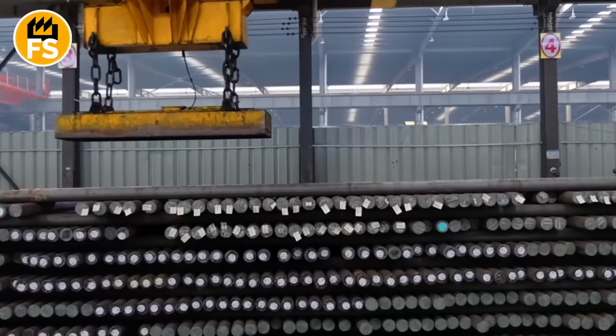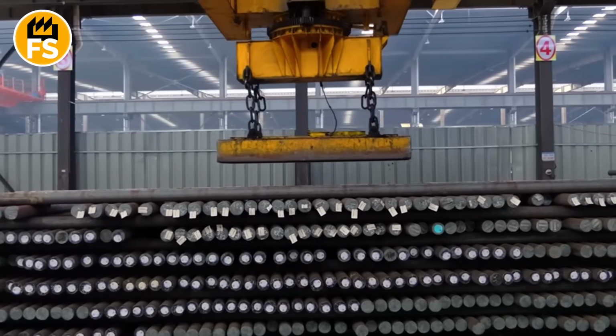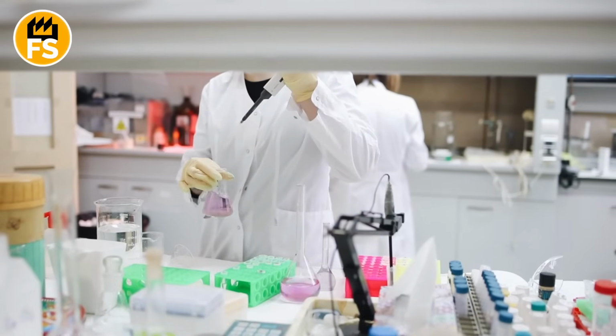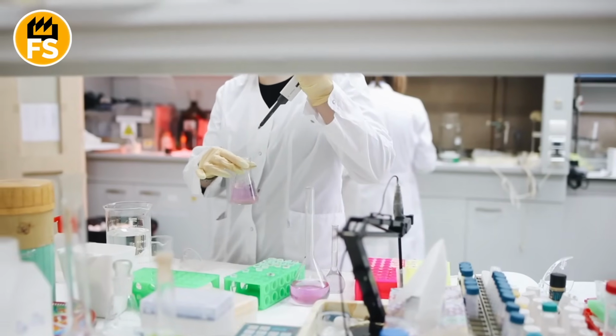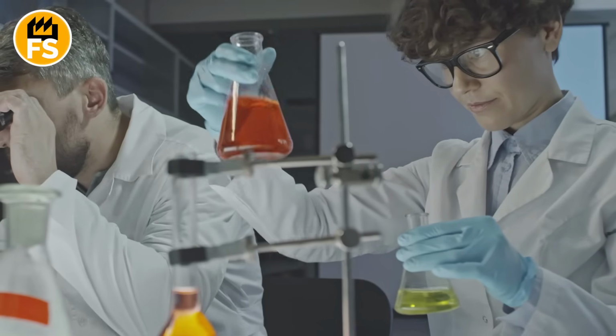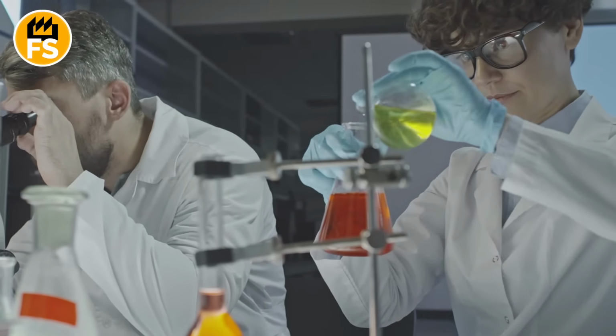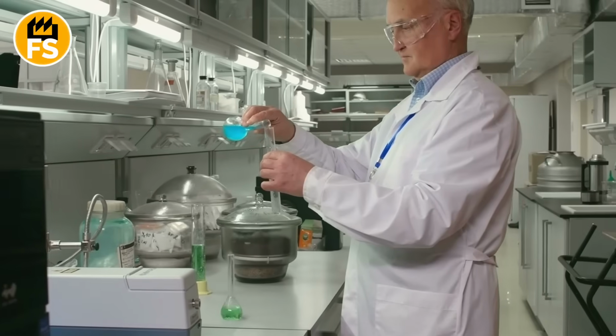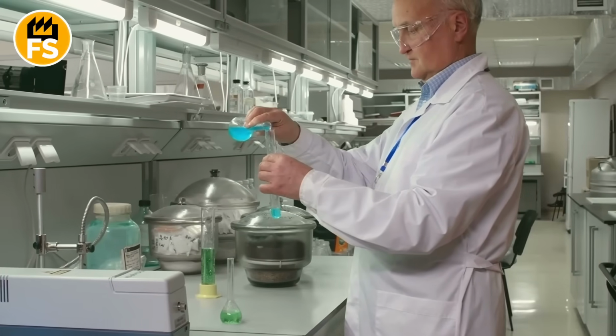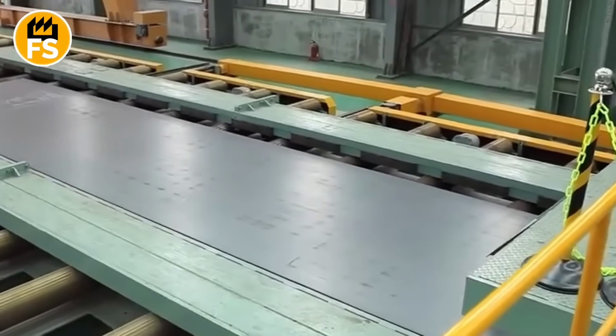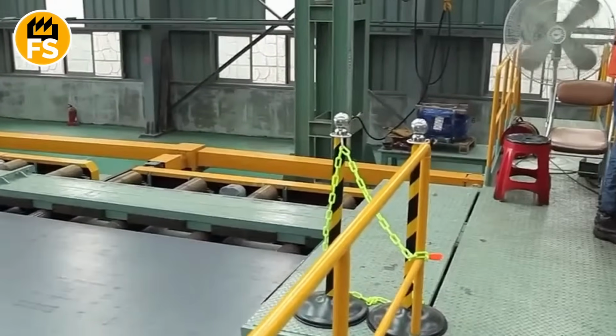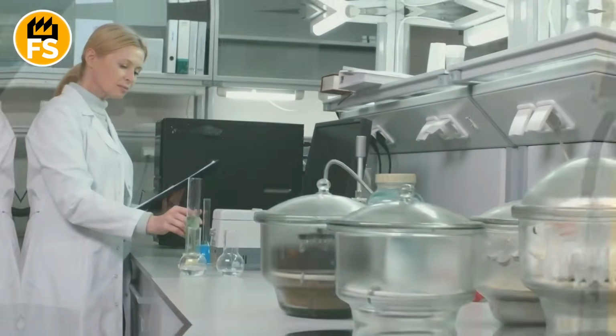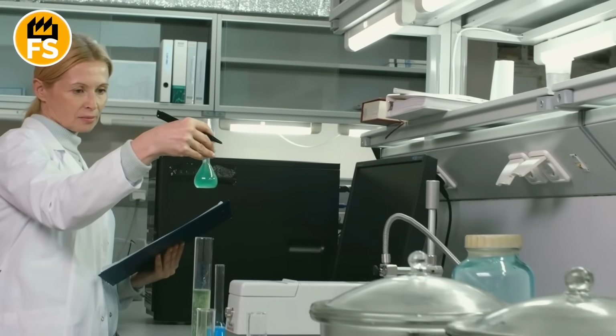Next comes the chemical analysis. For this, 5 or 10 metal samples are taken from each batch and sent to the factory laboratory. There, they use special spectrometers, devices that read the metal's composition using light emissions. The spectrometer determines over 12 elements in the composition in seconds. During the analysis, the sample is treated with an electric spark or a laser. This excites the atoms on the metal surface, causing them to emit light of different wavelengths.